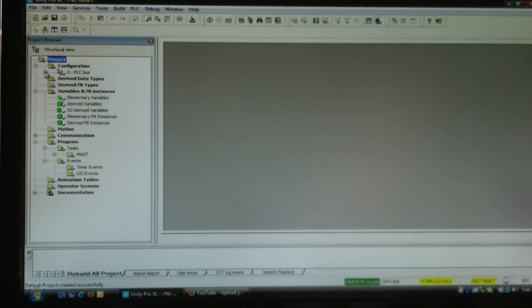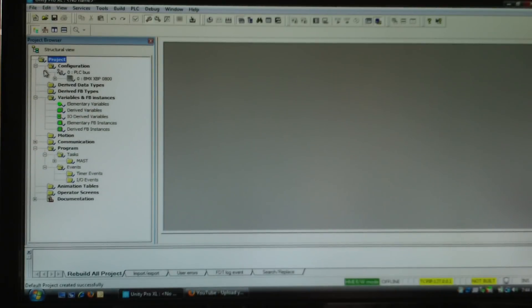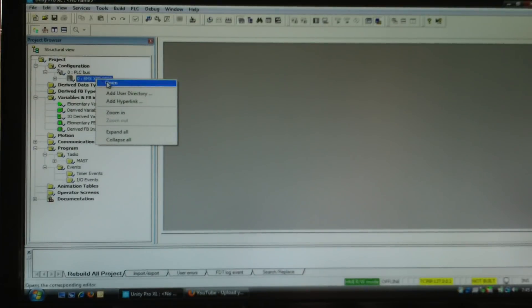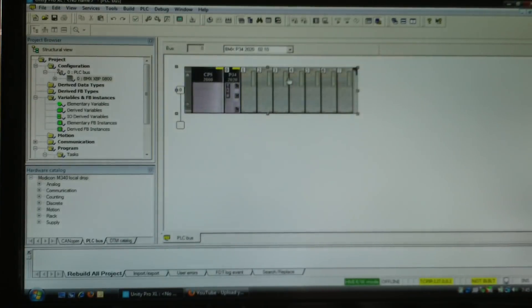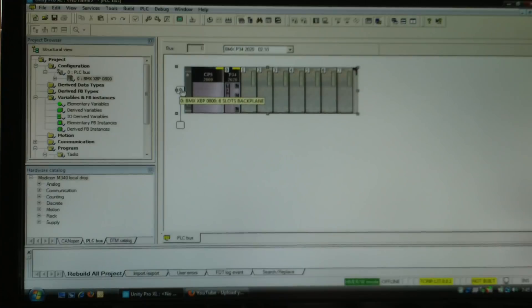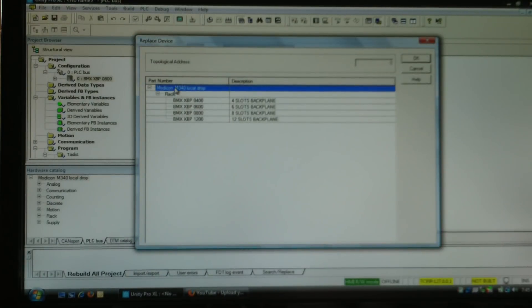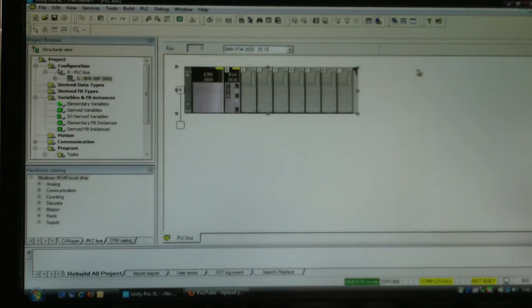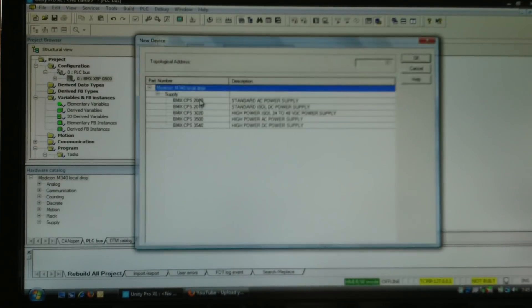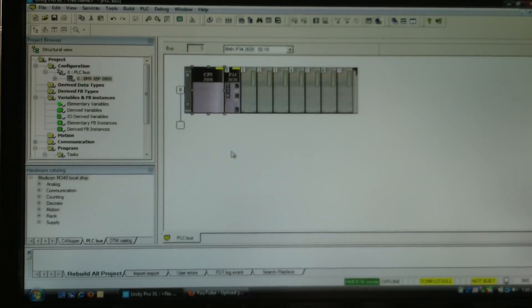I'm going to configure my hardware by expanding out the PLC bus and then right-clicking on the rack and going to open — or I could double-click on the rack. By default it gives you an eight-slot rack and a CPS 2000 power supply. If you want to change your rack, you double-click on this zero box here, which means rack zero.